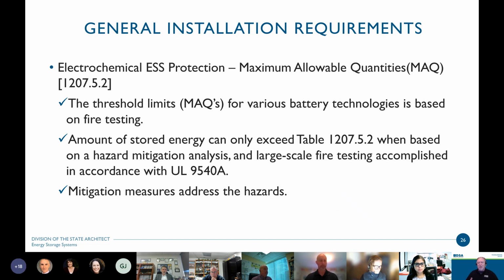Maximum allowable quantities, we're getting back to those items on the table again. When we talk about exceeding those quantities or those threshold limits, these threshold limits were established based on fire testing. The amount of stored energy can only exceed those listed on table 1207.5.2 when based on a hazard mitigation analysis and large-scale fire testing accomplished in accordance with UL 9540A. So we really want to make sure that those designs stay within those permitted thresholds so that the school districts aren't held up in getting these installed and complying with the energy code. And then, of course, we're going to look at mitigation measures that address the hazards. That's all what's going to be in that hazard mitigation analysis.